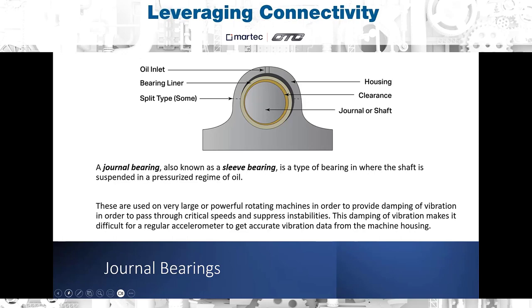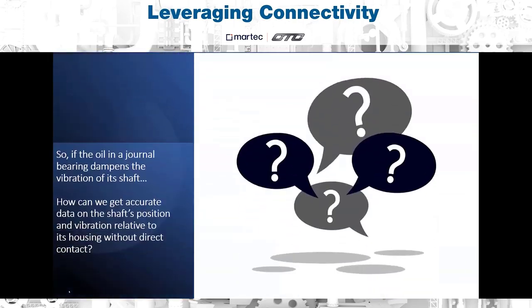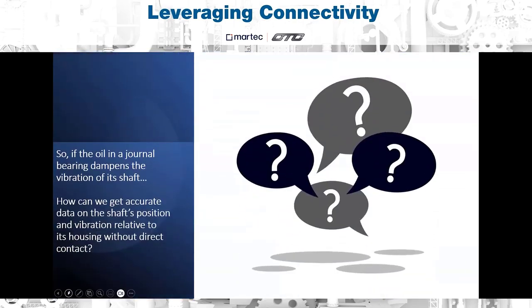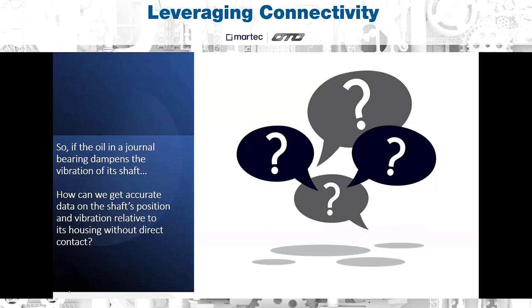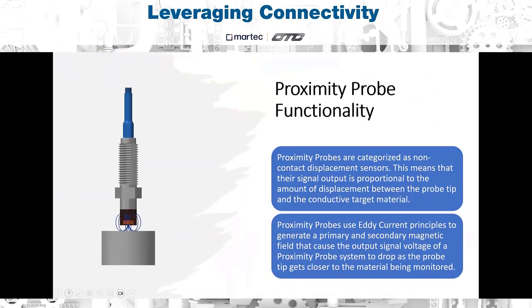While this oil does a great job dampening out some of that friction and preventing the vibration of the shaft from affecting the rest of the machine train, it also makes it very difficult to monitor the vibration of that shaft with traditional accelerometers. So that leaves us with the question, how can we still get accurate data on a shaft's position and vibration to perform predictive maintenance and condition monitoring without directly contacting the shaft itself? And the answer is proximity probe systems.